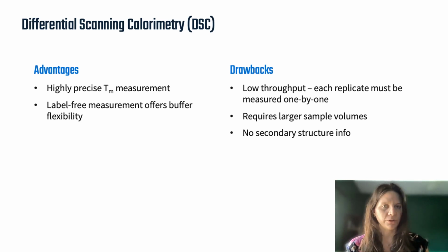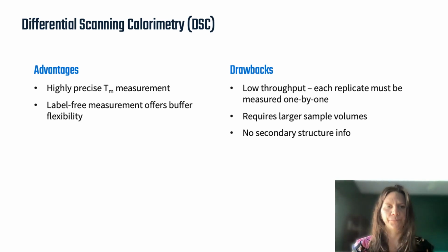For biologics researchers, though, DSC does indeed give highly reproducible, thermodynamically precise melting temperatures of therapeutic proteins, but it does have some downsides. The need for a reference sample for each experimental sample means preparing twice as much for any experiment. Further, most DSC instruments aren't really designed with high throughput in mind and just have the one space for the reference versus experimental sample, which means each experiment has to be done one by one.